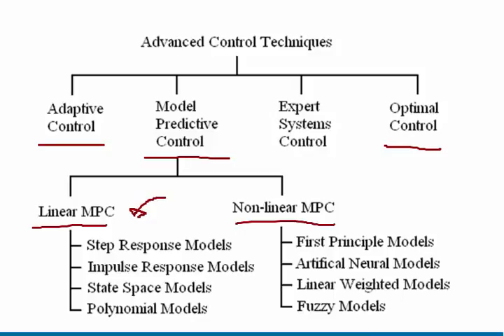The linear predictive model is a good way to overcome dead time and to change the process based upon a linear relationship. Where it gets more complicated is when you don't have a linear relationship — you may have an inverse squared or a sinusoidal relationship. The non-linear model includes artificial neural networks, linear weighted models, and fuzzy logic, which takes in multiple inputs, works out the relationship in terms of both steady state and dynamic, to find the interrelationship.